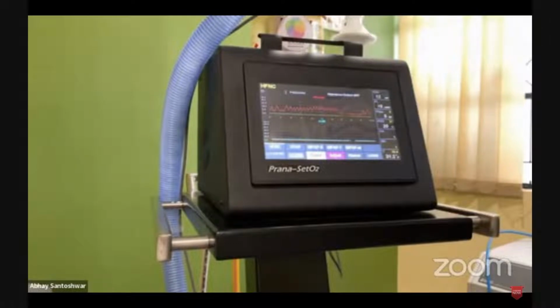When the patient is doing this way, I can very well say that he is starving for the gases. So I should increase the flow. So it is a very intuitive tool which can give us a guide into titrating the HFNC flows. Up till now, HFNC was a mode wherein flows were assumed. Like typically in adults, they used to use flows as high as 60 liters per minute. And when we studied it, we found that a normal adult is able to breathe in comfortably on 35 to 40 liters per minute. That's a net saving of 20 liters per minute.